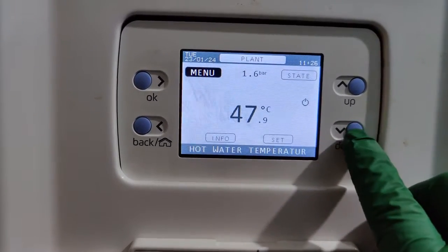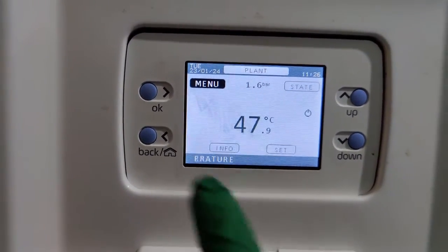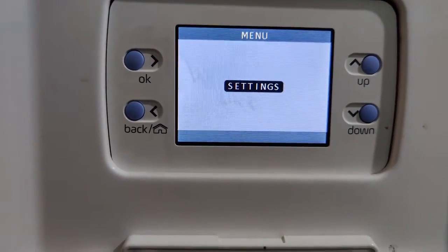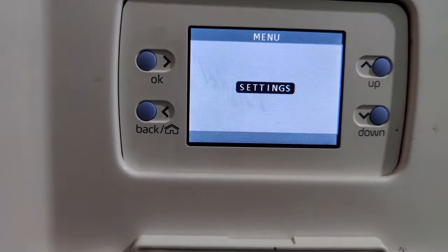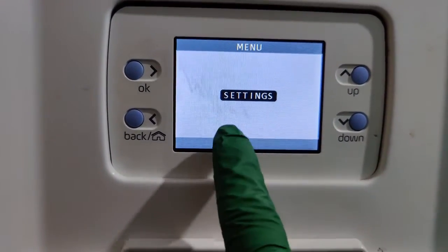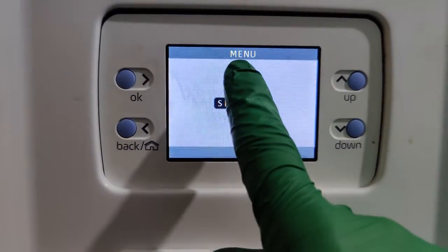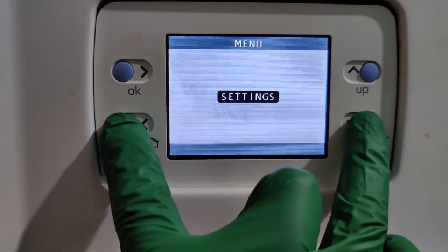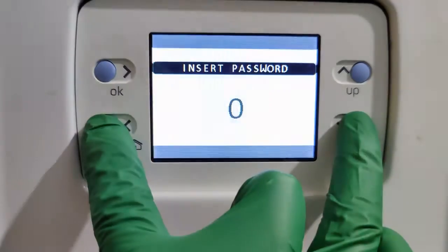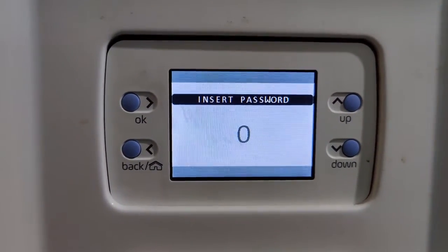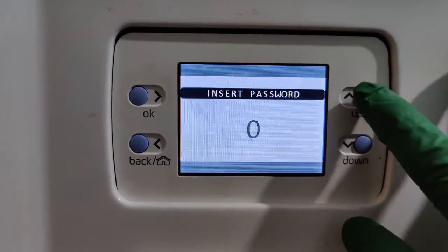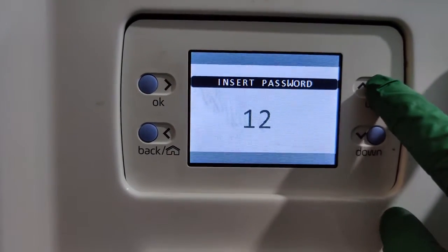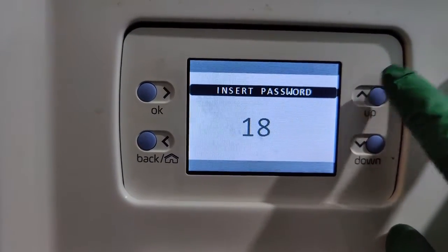Our objective is to go to Combustion Analysis and get the high and low readings. Go to Menu, OK. It only shows the Settings menu — user settings, date and time, etc. — so we need to get to Technical. While on the Settings screen within Menu, press and hold Back and Down together. It will then ask for a password. This is an engineer's password — this video is for registered engineers and competent people only, not customers or users.